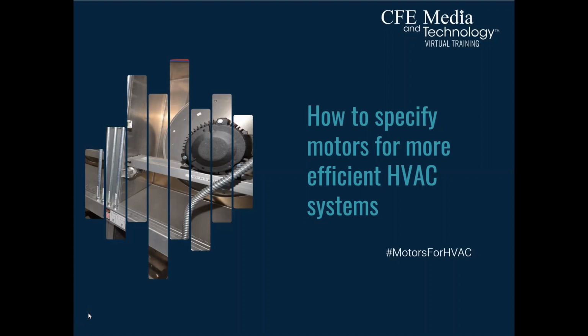While adding VF drives is a common practice, the capability of doing this is if you have a system that has a constant volume, no matter what the speed is, and you can start considering replacing the drive with a standard starter.